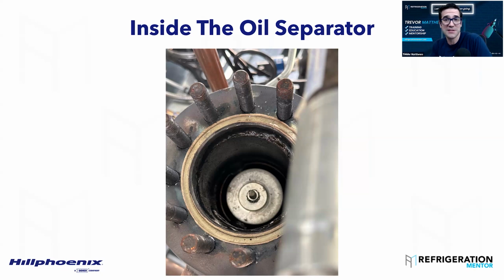This is where you're doing all your checks, you know what I mean? So you're doing evacuation, but you've got your pressure probes, like you said already, all your temperature probes. You check your phase monitor, make sure that works. You check all your relays. So you override, say, the liquid injection relay, make sure it turns on and off, your oil level controls. There's a process to do that. And maybe we could talk about that quick when you're adding oil to the system.